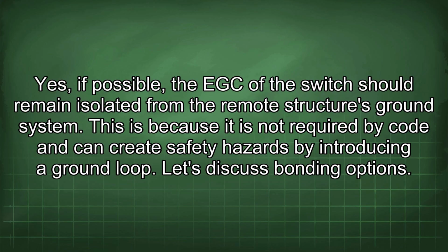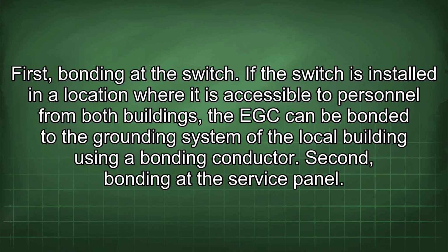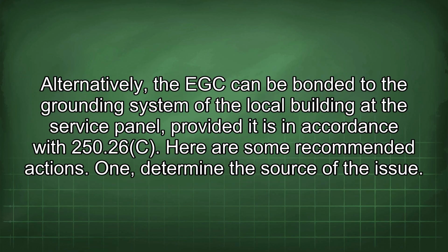Let's discuss bonding options. First, bonding at the switch. If the switch is installed in a location where it is accessible to personnel from both buildings, the EGC can be bonded to the grounding system of the local building using a bonding conductor. Second, bonding at the service panel. Alternatively, the EGC can be bonded to the grounding system of the local building at the service panel, provided it is in accordance with 250.26c.